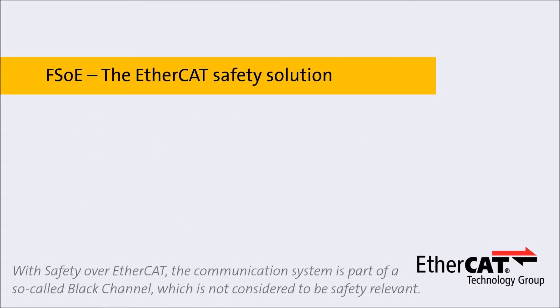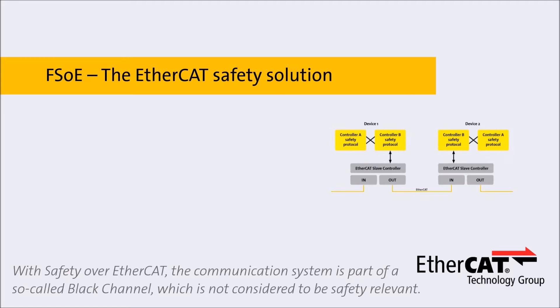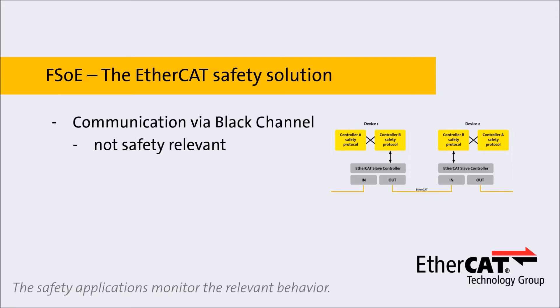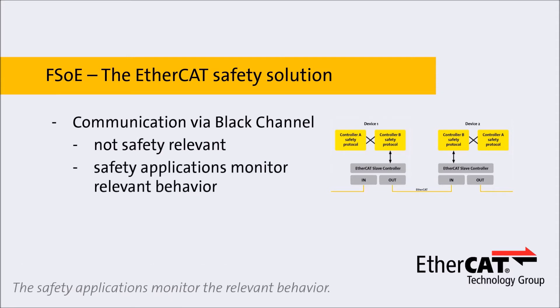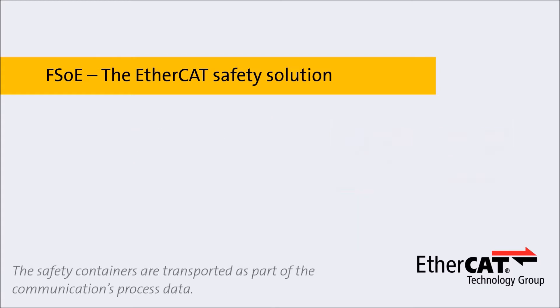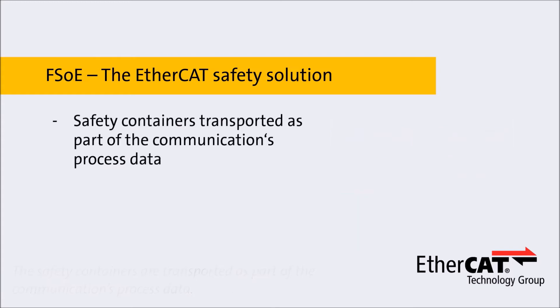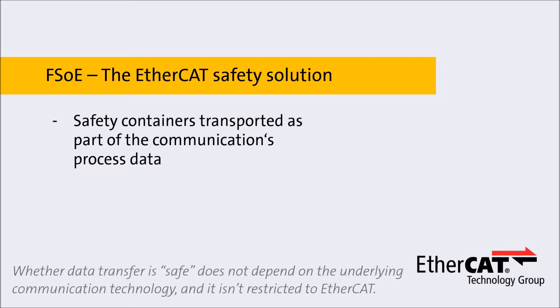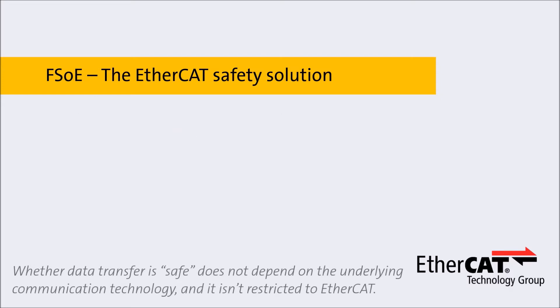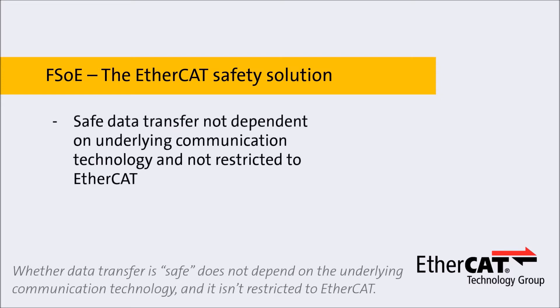With Safety over EtherCAT, the communication system is part of a so-called black channel, which is not considered to be safety relevant. The safety applications monitor the relevant behavior. The safety containers are transported as part of the communications process data. Whether data transfer is safe does not depend on the underlying communication technology.